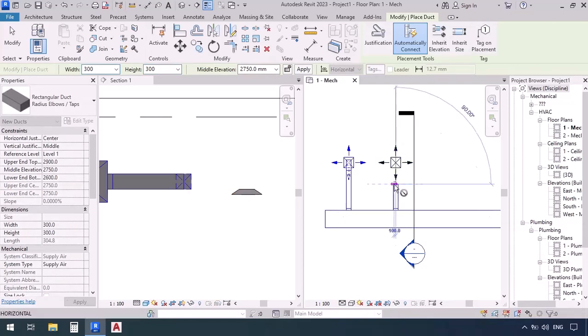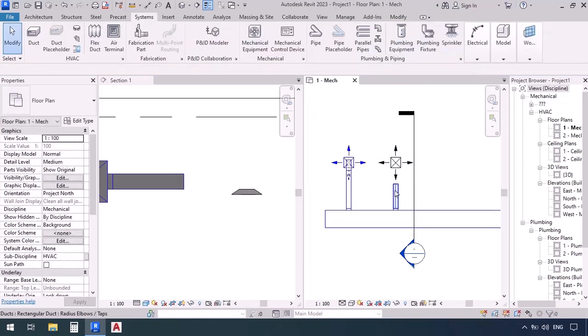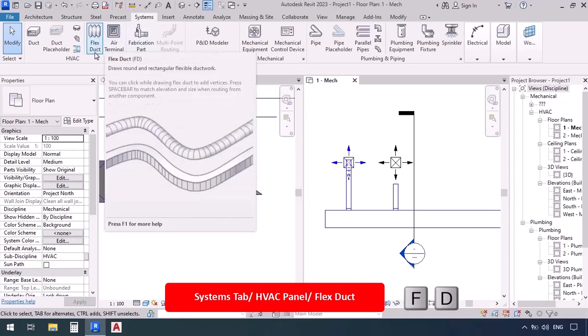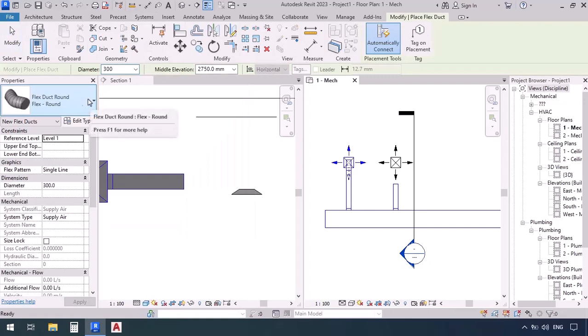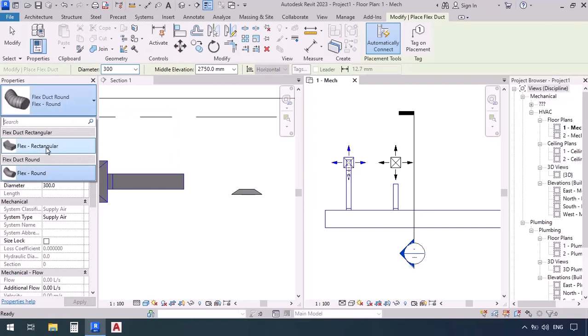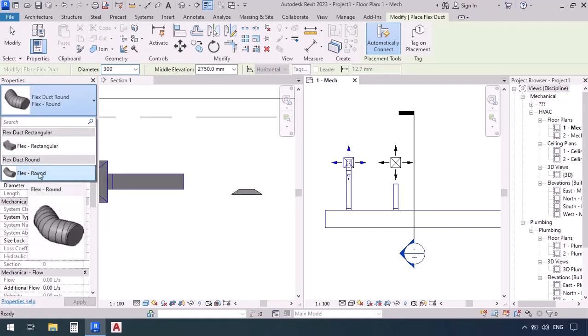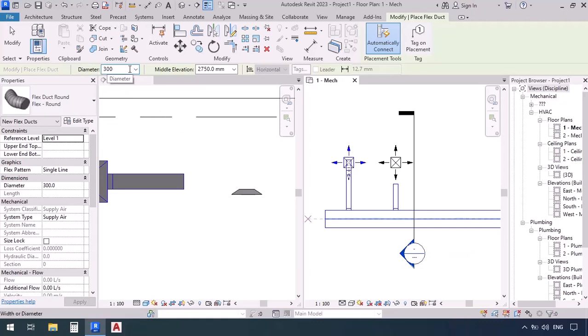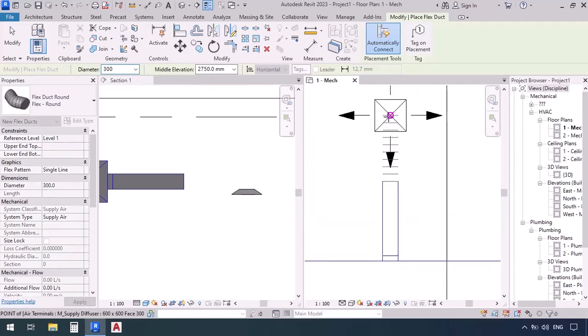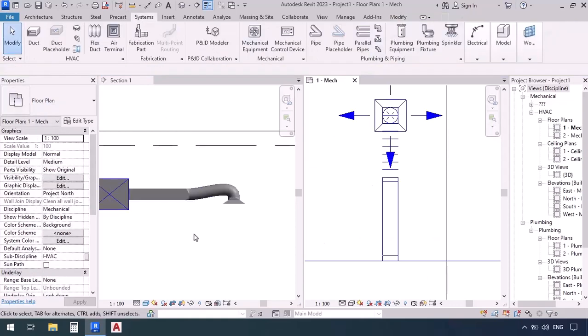I'll click and then somewhere near the terminal for the second click, then press escape — so now we've drawn one single direct duct. Now we go to the systems tab and click on the flex duct command. This is a tool for drawing flexible ducts in the project. In the properties window we can use flex rectangular or flexible round, which is circular. Always make sure the system type of your terminal matches the system type of your duct. Starting from the end of this duct, click and right until the axis of the terminal, click again, then press escape — it connected a flexible duct for us.